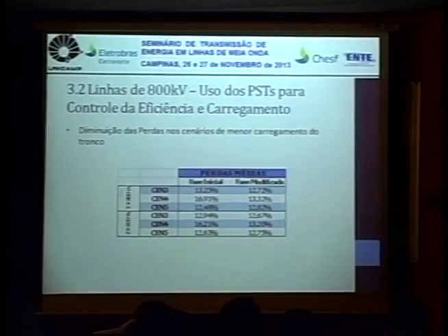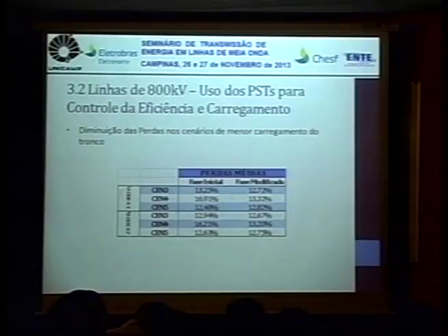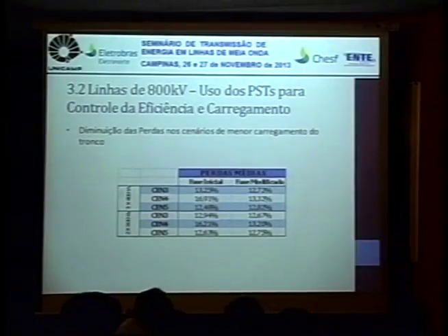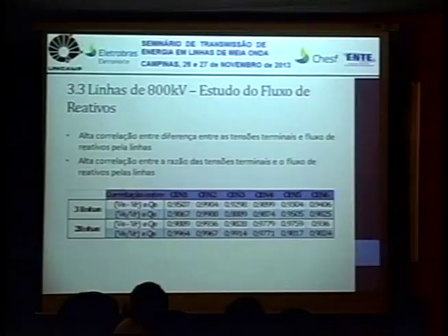So we are working in that 30 degrees range besides the 180 degrees, which is a natural correction of the half wavelength. So we do simulations and find the out of phase point to minimize losses. So this would be, even if it is manual work, the operating point where losses would be minimal for each of those scenarios, ensuring that the power flow in the line is close to the reference that's established for each of the scenarios created by EPE.